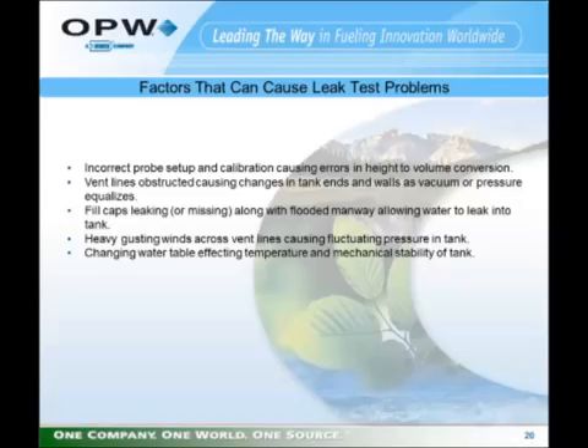If vent lines are obstructed, that can cause changes in tank ends due to pressure or vacuum, which can affect a test. Fill caps leaking, or heavy gusting winds across the vent could cause product to start moving back and forth, wave action in the tank. A changing water table: as the water table comes up and down around the tank, it can cause great temperature differences to appear in the tank. Those can all affect leak tests.